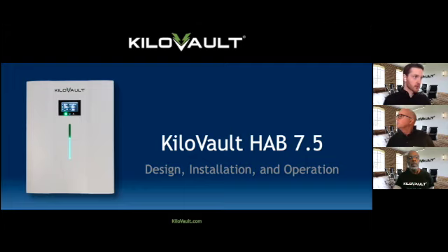I'll hop in and answer Daryl's question in regards to the commissioning charge. 56.4 volts is the recommended absorb voltage. To get to 100% state of charge, the manual recommends an absorb time of, I believe, Marlin, 2 minutes or less, depending on charge rate. So pretty much once you've reached 56.4, the batteries are effectively full. I would say refer to the manual for recommended absorb time given charge rate. But for the commissioning charge, once you get each to 56.4, they should be all pretty close. We're talking 97 to 100% state of charge. Right. With these batteries, they don't really need to absorb like other chemistries do. Once you're there at the voltage, it's fully charged.